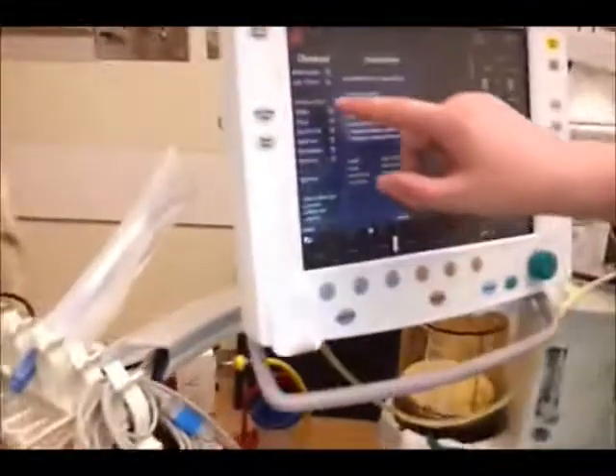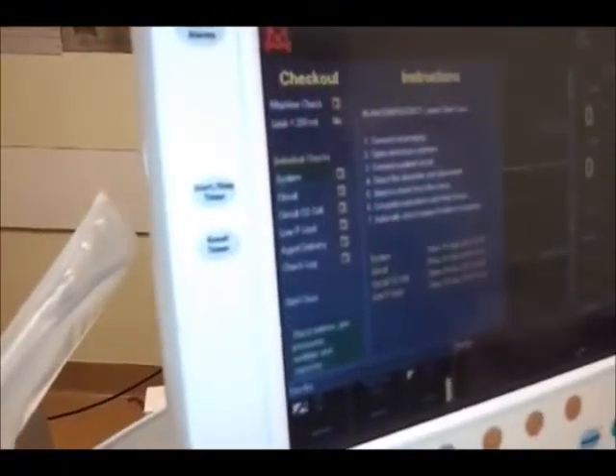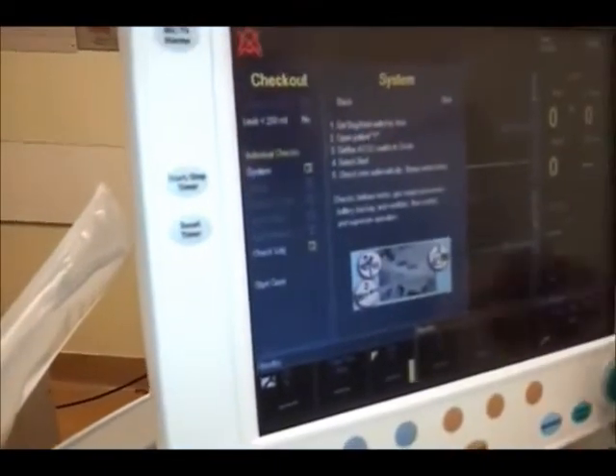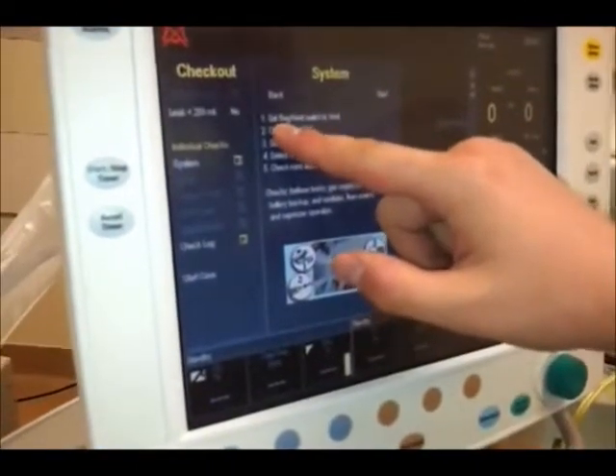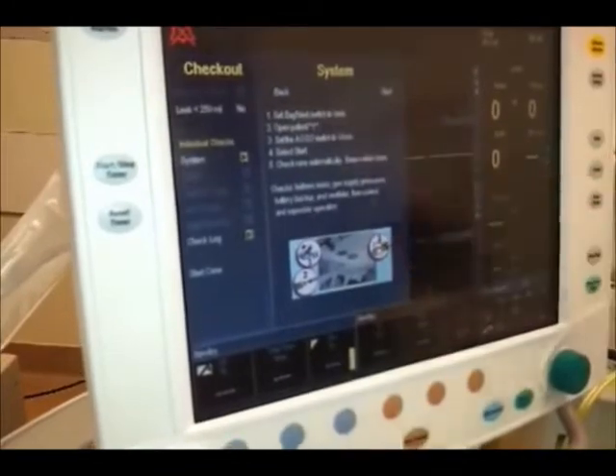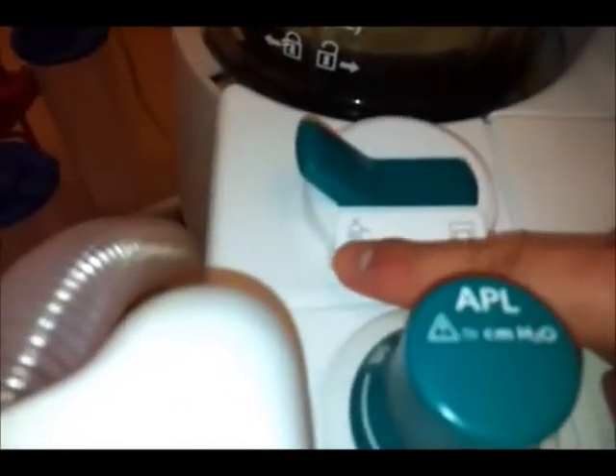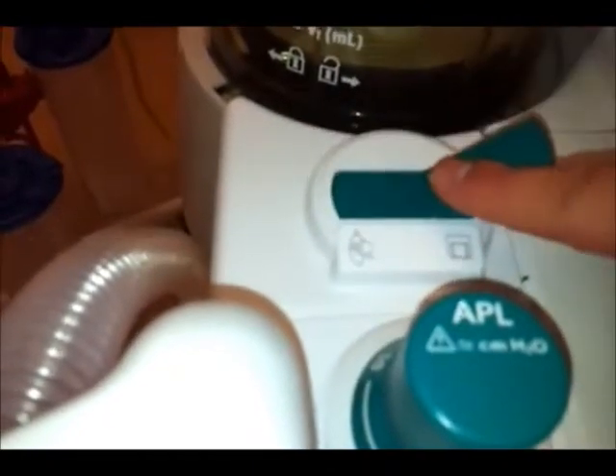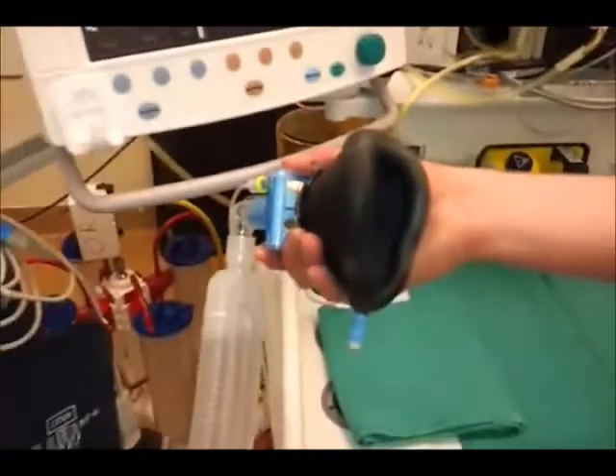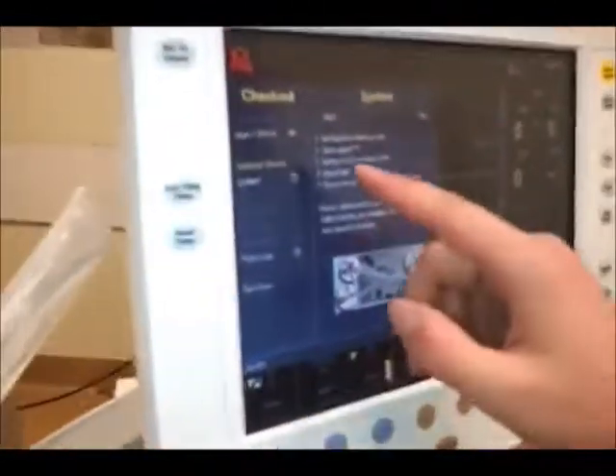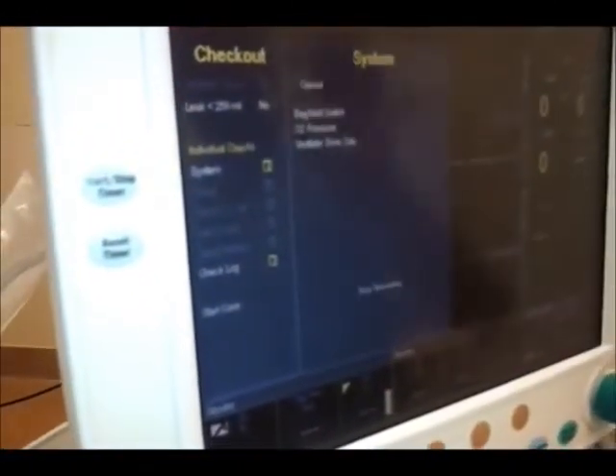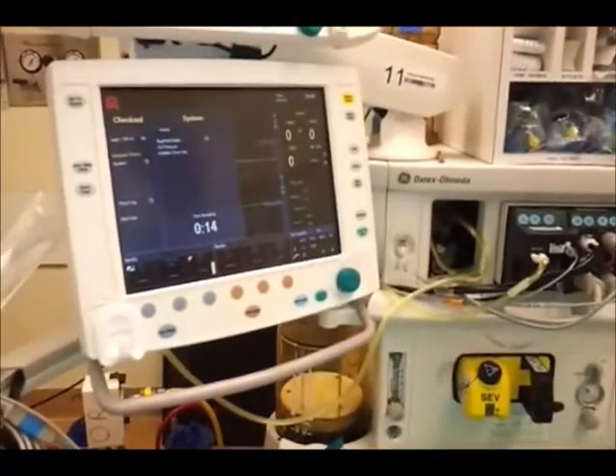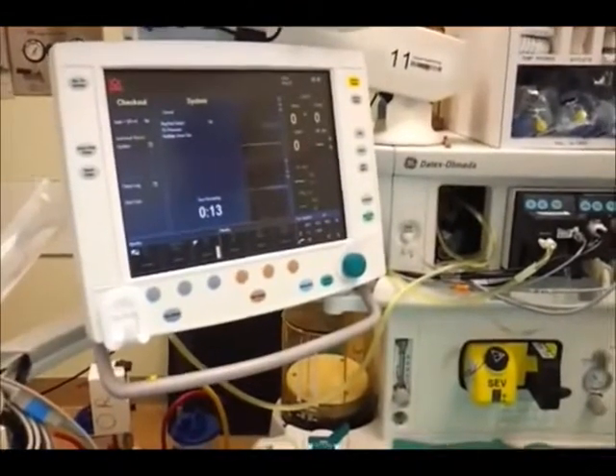Okay? So the next check you have to do is the system check. Once again, it tells you what to do. Set the bag/vent switch to vent. So that's right back here. You can see a little picture of the ventilator, and the bag. It's set on bag right now, so you're going to shift it over. You want the patient Y opened, so you want this open to atmosphere, and then start. So basically you just have to hit start. This one only takes about 20 seconds. So we're just going to let it go.